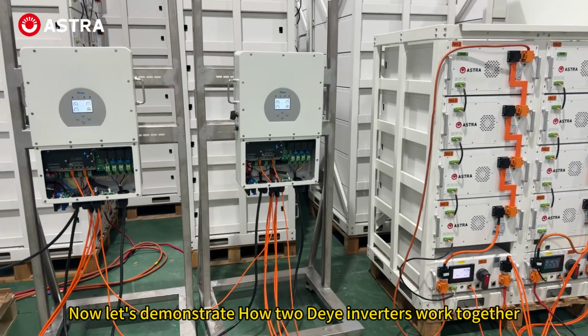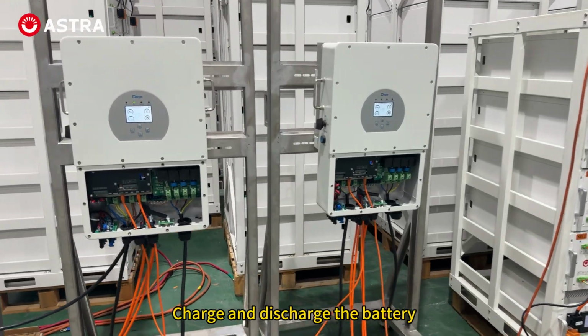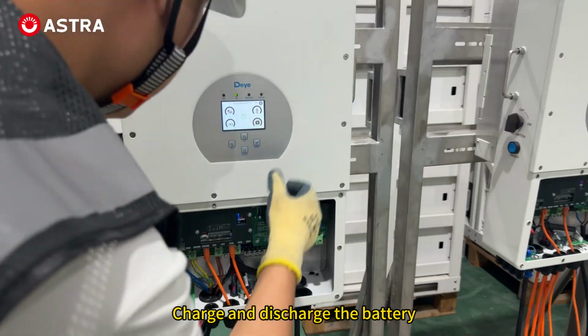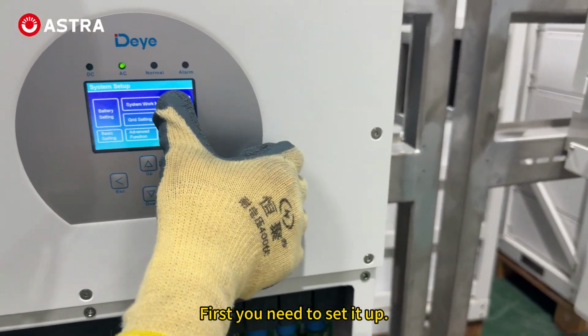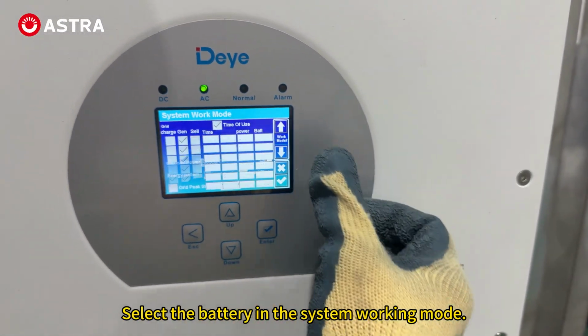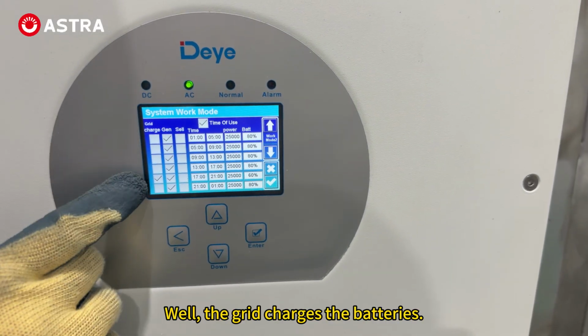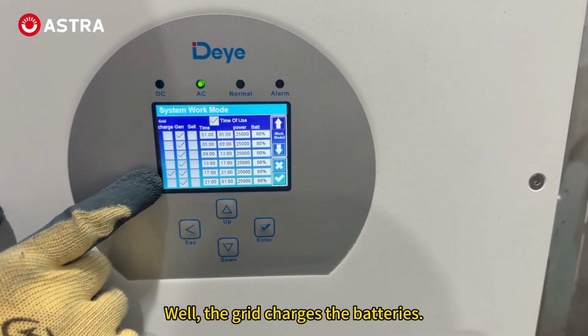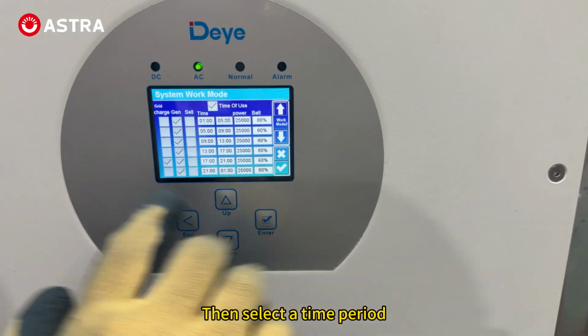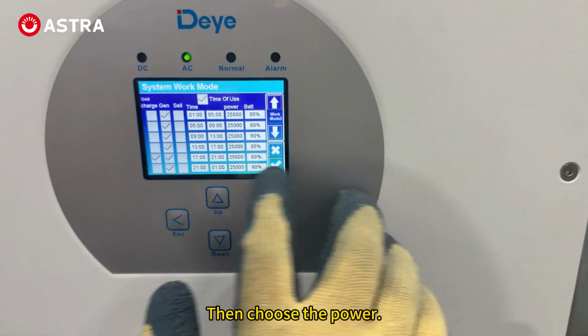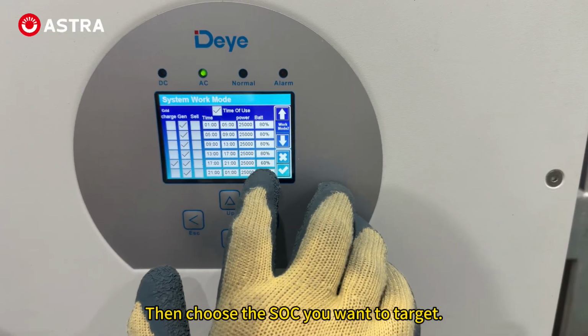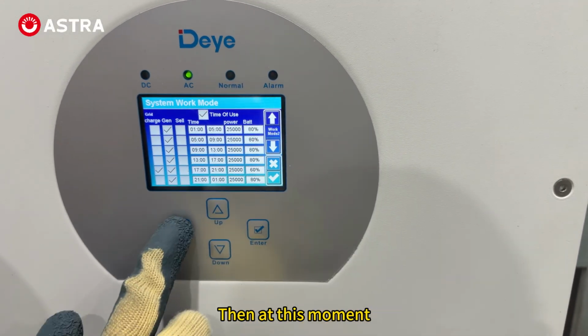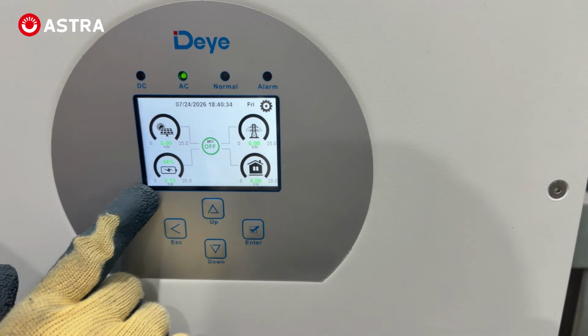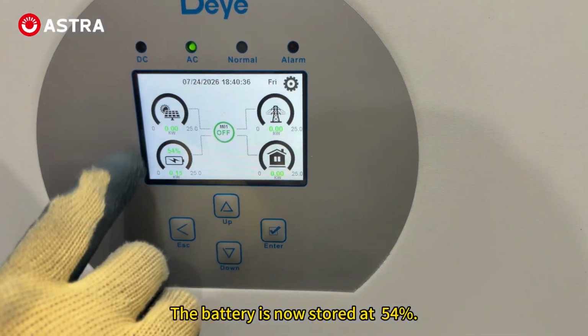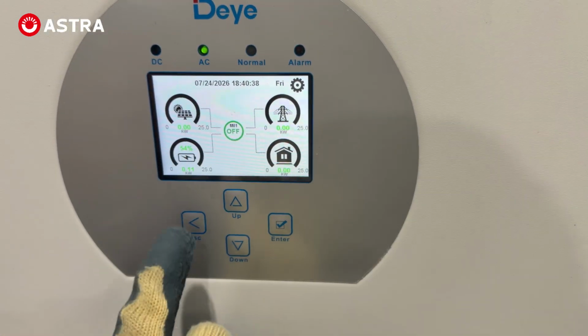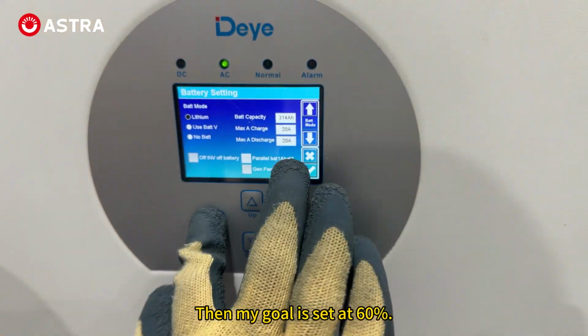Now let's demonstrate how the 2 inverters work together to charge and discharge the battery. First you need to set it up. Select the battery in the system working mode. Well, the grid charges the batteries. I've ticked it now. Then select a time period. Then choose the power. Then choose the SOC you want to target. At this moment, the battery is at 54%. Then my goal is set at 60%.